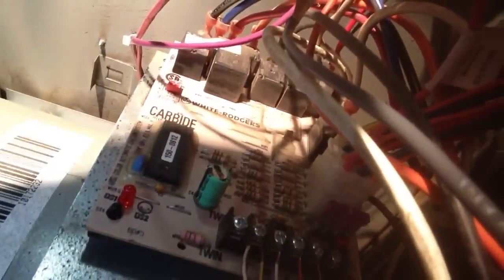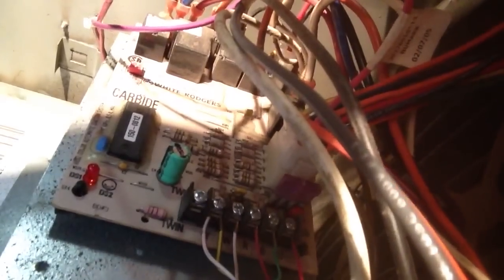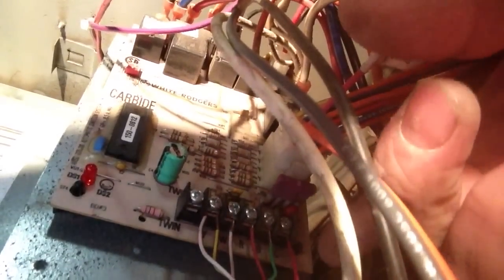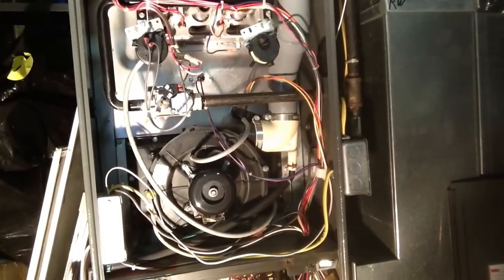Now you see that little light and that red light. Steady on means it's ready to go, working good. No light, no light, bad board or bad fuse, or no power. If this light blinks continuously, it says you have your polarity reversed, which means your white and black wire are switched. Which I've never seen that, but that's what it says. That's what that is. Okay, that's all your trouble codes and basically where they're at on the furnace.